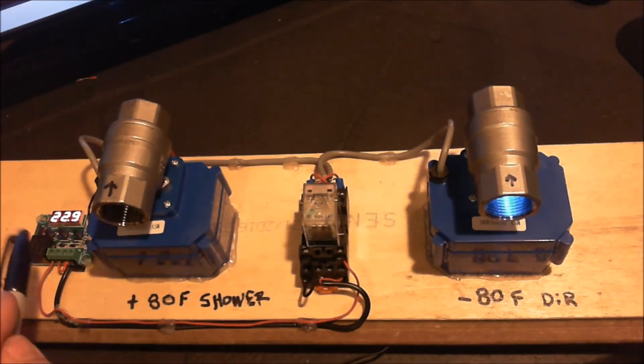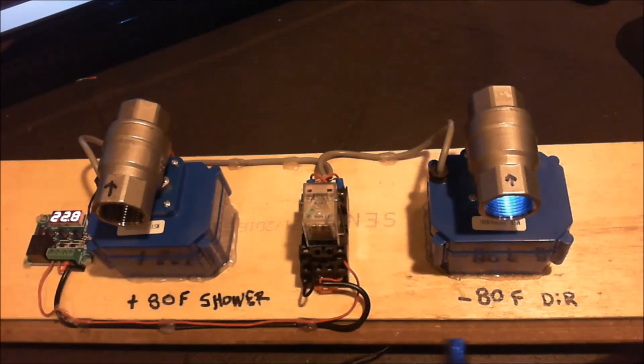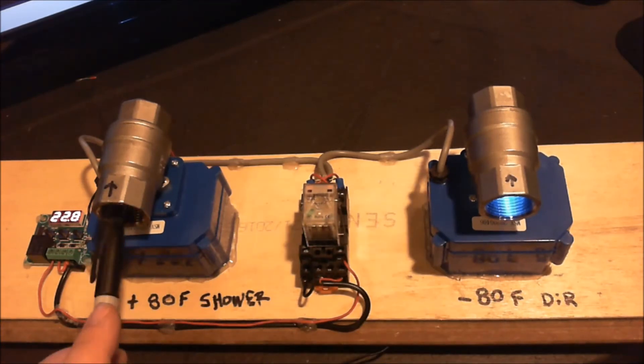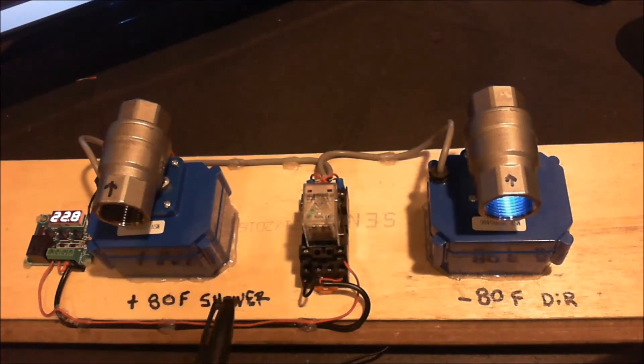So at 22 degrees Celsius, which is somewhere around 72 degrees Fahrenheit, I want this valve to open until the pool water temperature reaches about 80 degrees Fahrenheit and then at 80 degrees Fahrenheit the water will now go through the shower head allowing some of that heat energy to dissipate into the atmosphere, thus bringing the temperature of the pool water down below or about 80 degrees Fahrenheit.